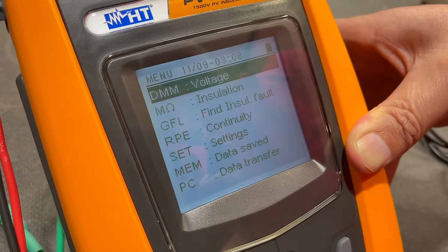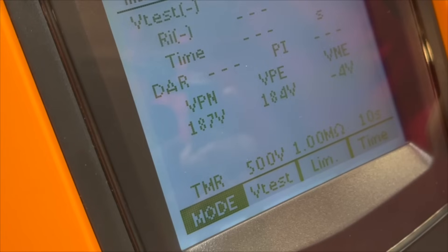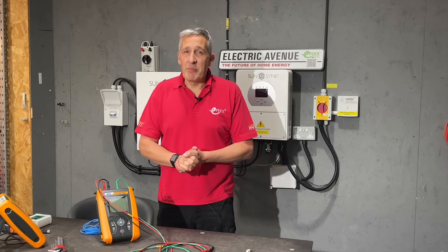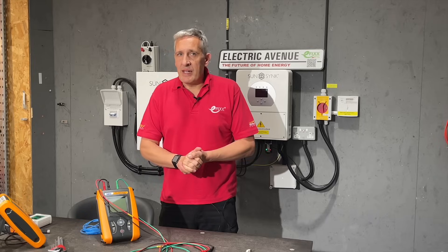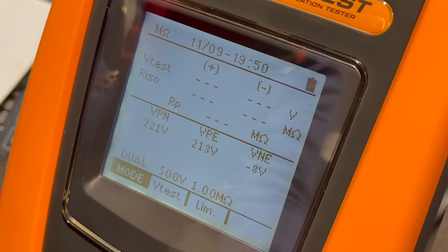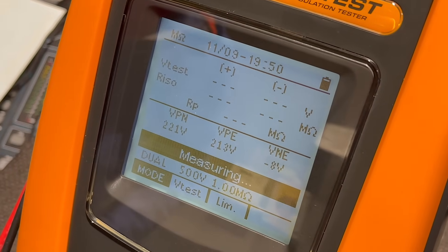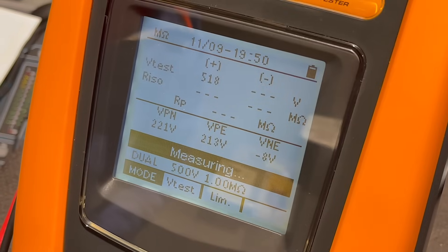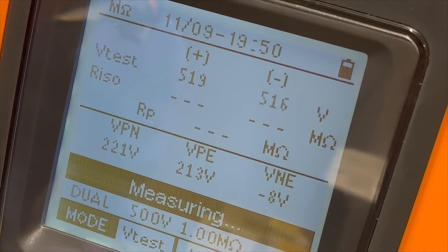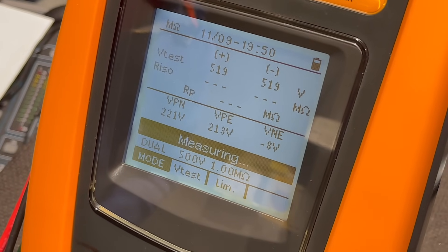Once connected, we select the insulation test setting. We're going to start with the dual mode, which measures insulation resistance between both the positive and negative cables and earth. To start the test, we press and hold the go button for two seconds. As the test starts, we see the test voltage applied to the positive and negative lines, and we can also see the voltage being produced by the modules at the same time.